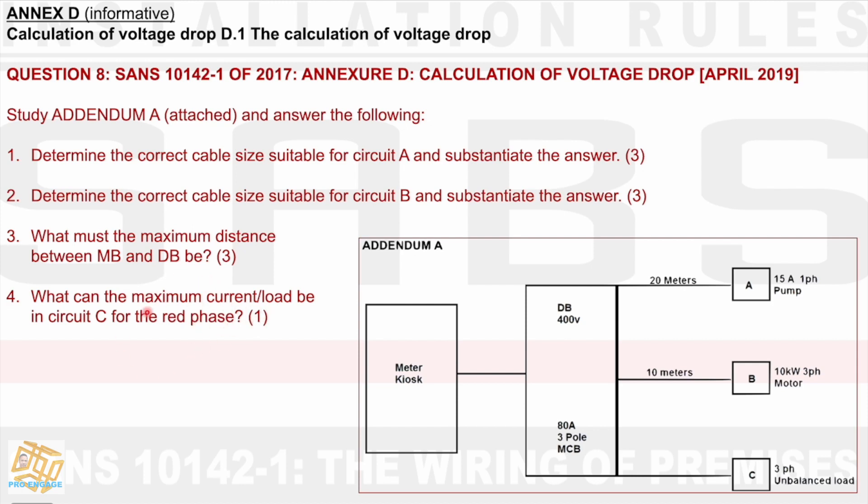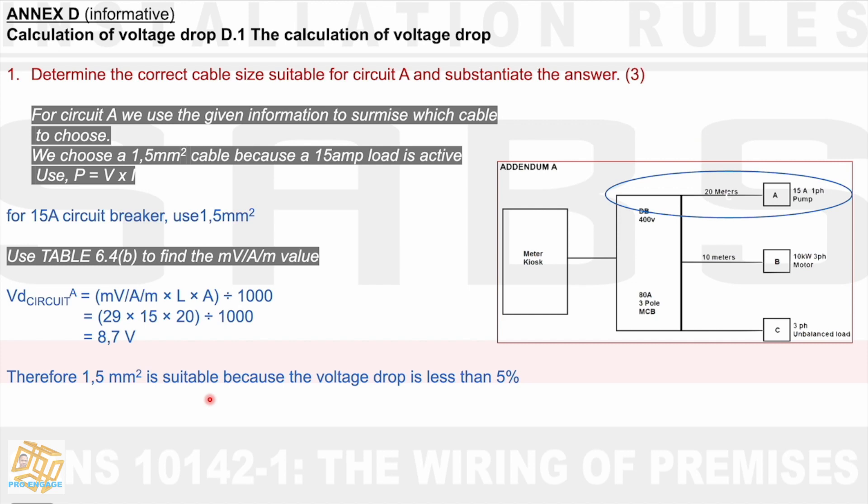For one mark it's going to be a simple formula or simple derivative. We're going to just assume here or make up a formula which is a standard thing. Let's see where this calculation takes us. Determine the correct cable size suitable for circuit A and substantiate the answer. For circuit A, we use the given information to surmise which cable to choose. And we choose a 1.5 mm² cable because a 15A load is active. I understand that the maximum circuit breaker for 1.5 mm² cable is 15A. Here they give us a 15A pump. We say that circuit is going to operate on max. We say we use 1.5 mm².